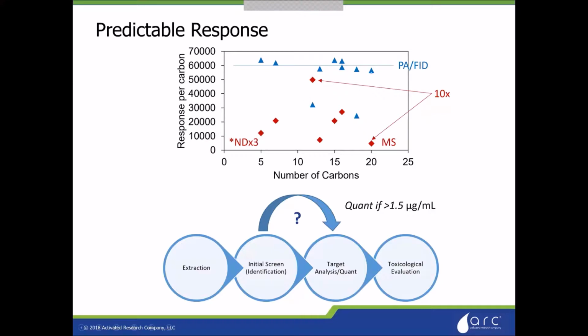The polyarc FID, because we're converting everything to methane, you have a uniform response, you have a predictable per carbon concentration response. So you can very quickly screen samples and determine if they're above or below certain thresholds. You also have a pretty uniform limit of detection that essentially only depends on the amount of peak broadening you're having.